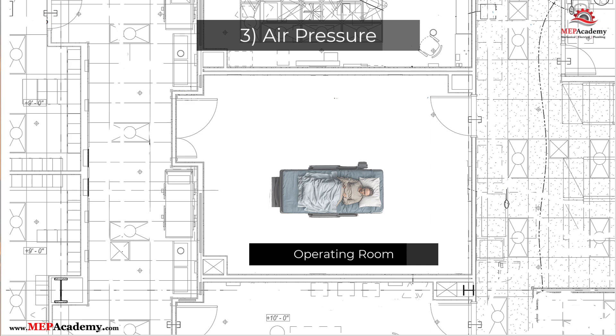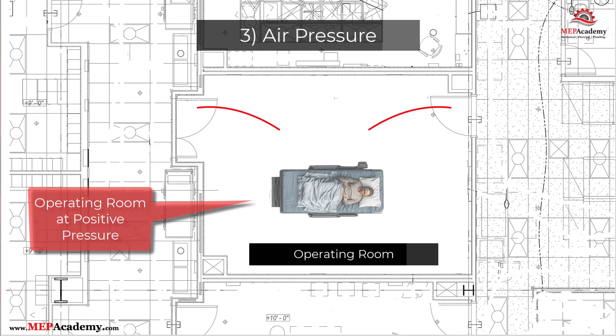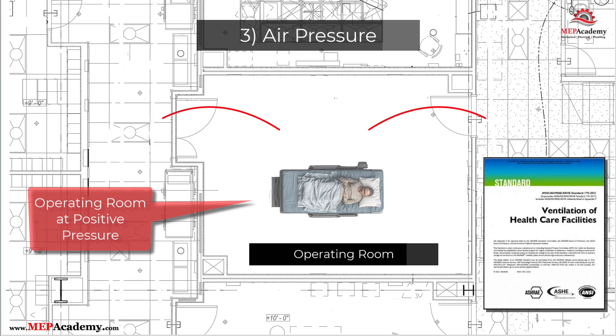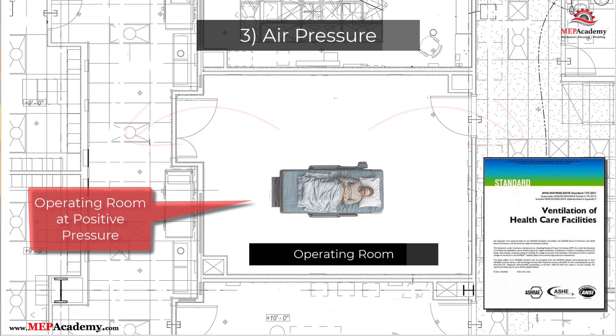Takeaway 3: Pressure relationships are engineered to prevent contamination. An equally important part of OR HVAC design is managing room pressure relationships. In a surgical suite, air should always flow from the cleanest areas to the less clean areas. That means the operating room itself must be kept at a positive pressure relative to adjacent spaces. According to ASHRAE 170-2021, the operating room must be maintained at a minimum positive pressure differential of +0.01 inches water gauge relative to adjacent areas, including corridors, ante rooms, scrub areas, and nursing stations.